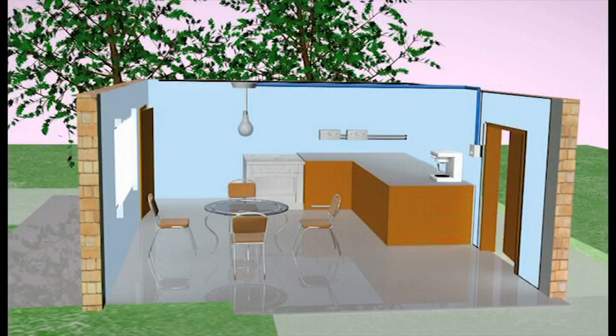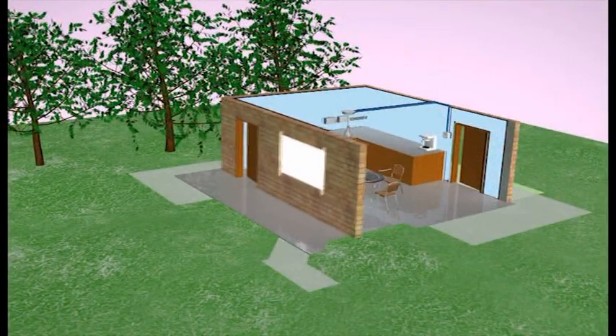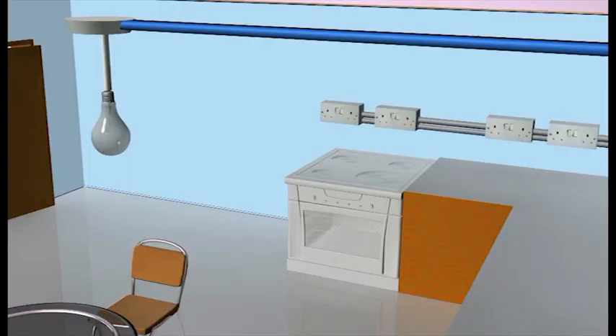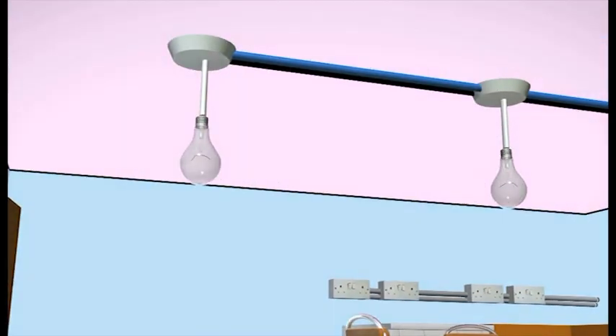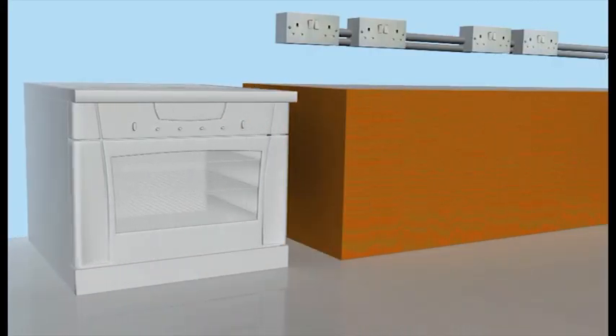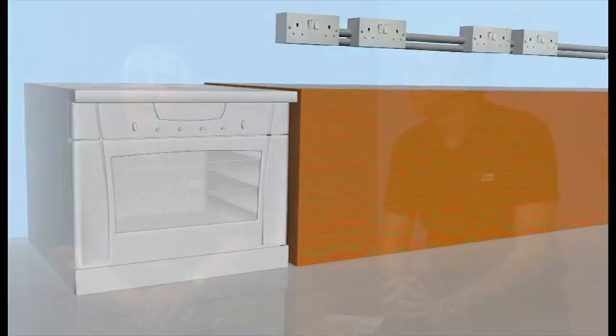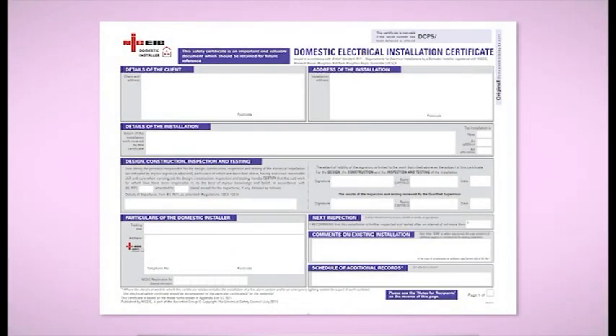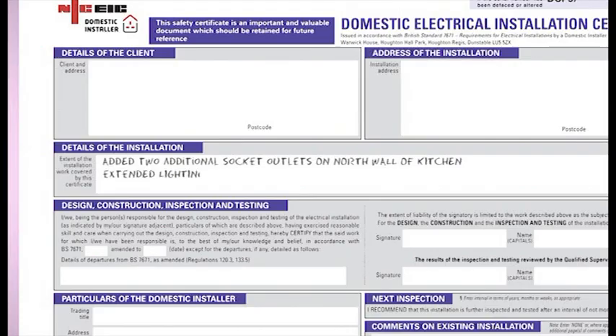So, for example, you might use it when extending an existing circuit, say a ring final circuit into an extension. But you have to use a minor work certificate for each and every circuit you work on. So if I also extended a lighting circuit into that very same extension, I would have to use 2 minor work certificates. And if the extension was a kitchen and I extended the existing cooker circuit into it, I'd have to use yet another one. So what you're saying is that in the example you've just described, instead of 3 minor work certificates, it would make much more sense to use an electrical installation certificate and list the details of the circuits being worked on in the details of the installation box.